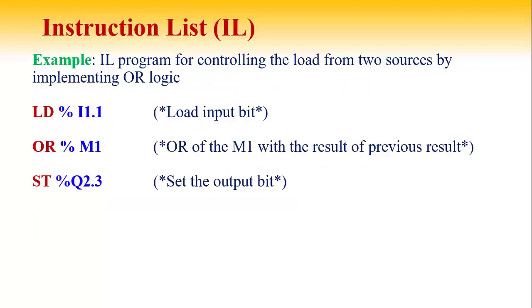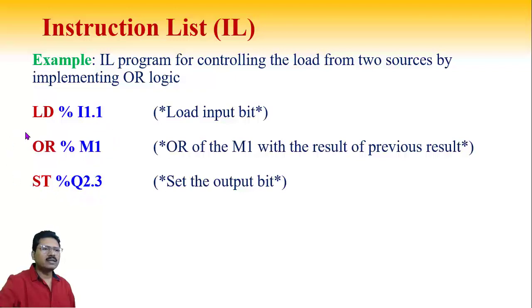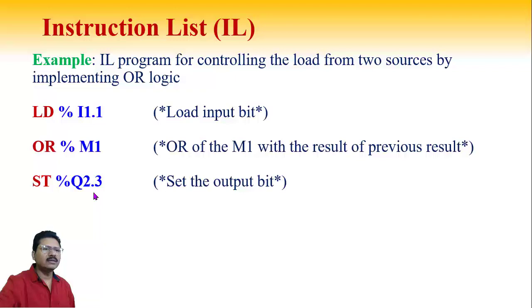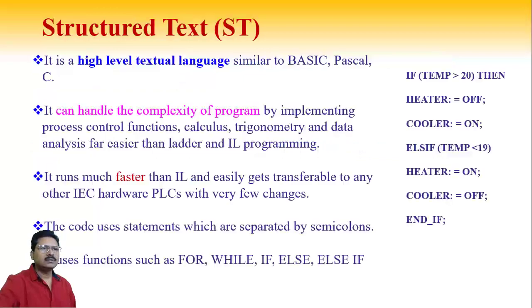Here is one example program using Instruction List: LD I0.1, OR M0, ST Q2.3. These are just like mnemonics used in microprocessor programming. I0.1 is the address of an input; M0 is a memory bit, and OR means performing an OR operation with the status of input I0.1. Ultimately, the result will be stored at the memory location specified by output Q2.3.